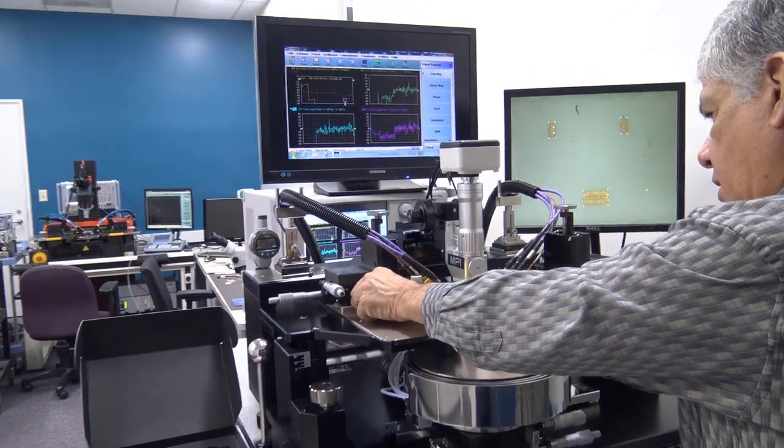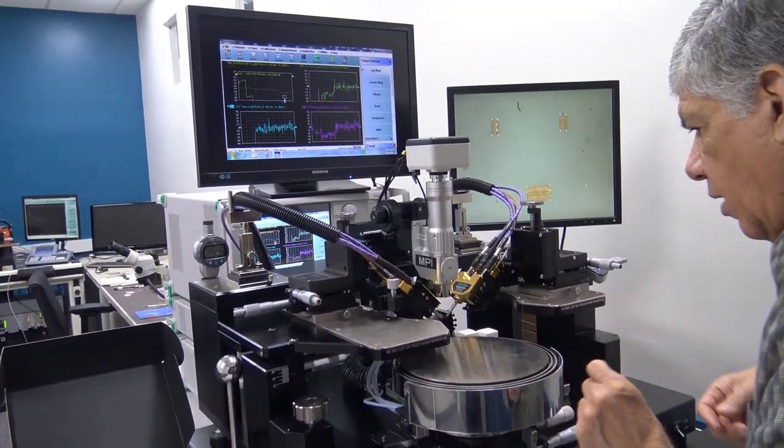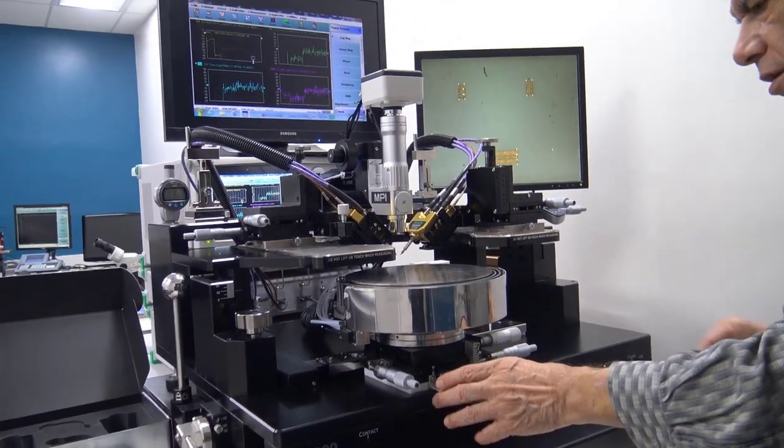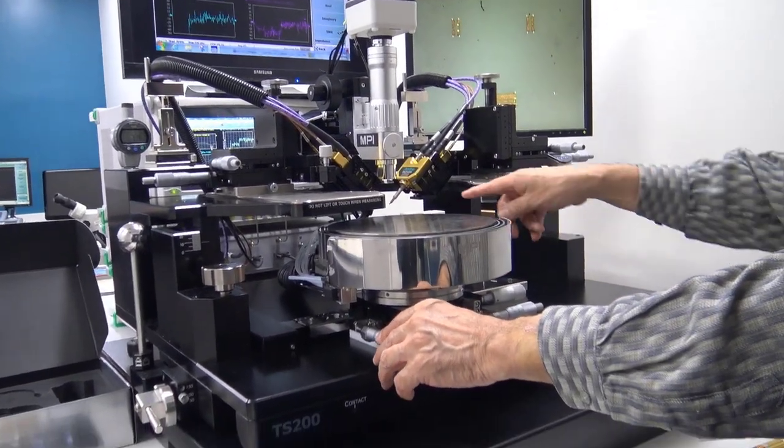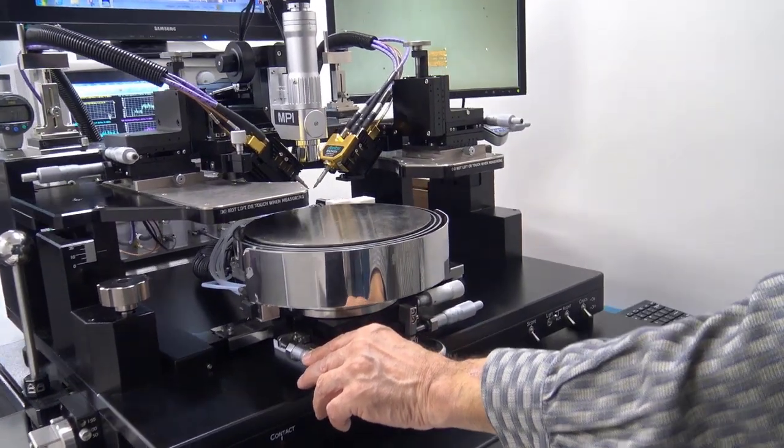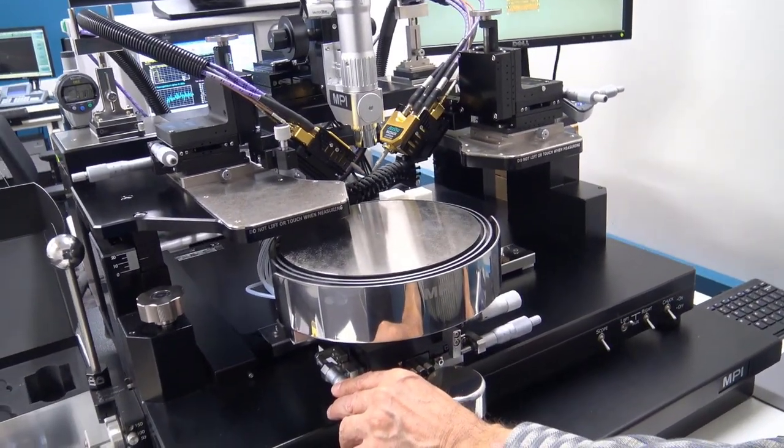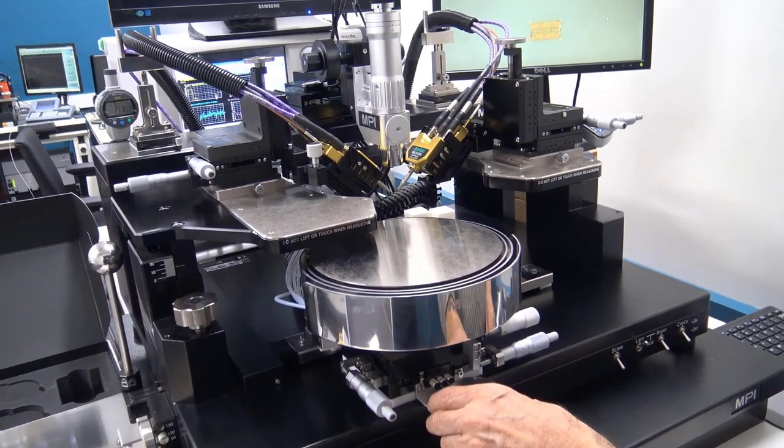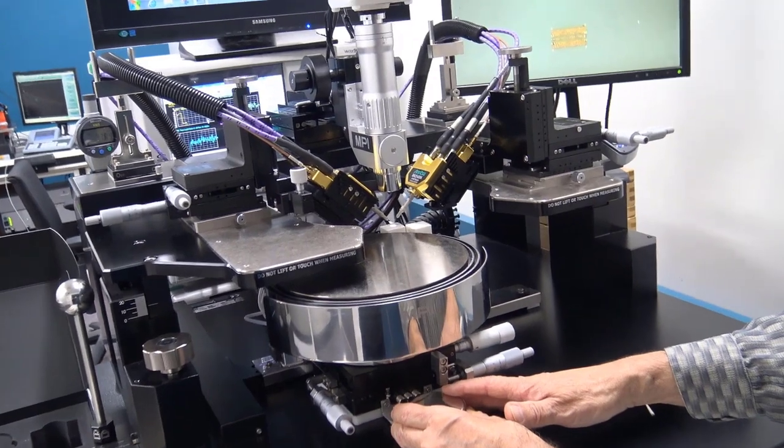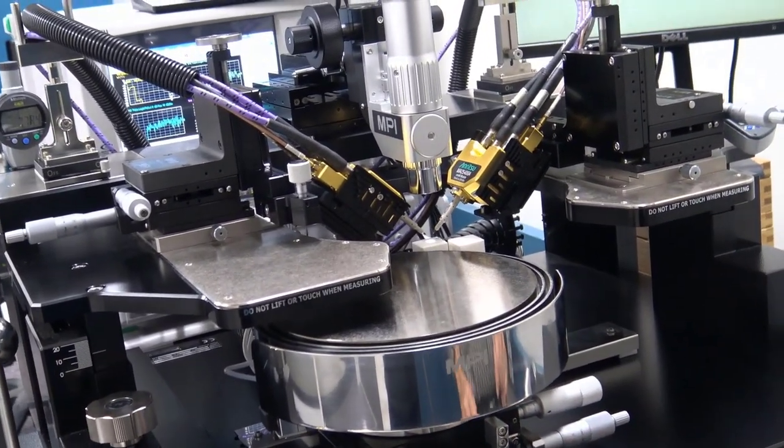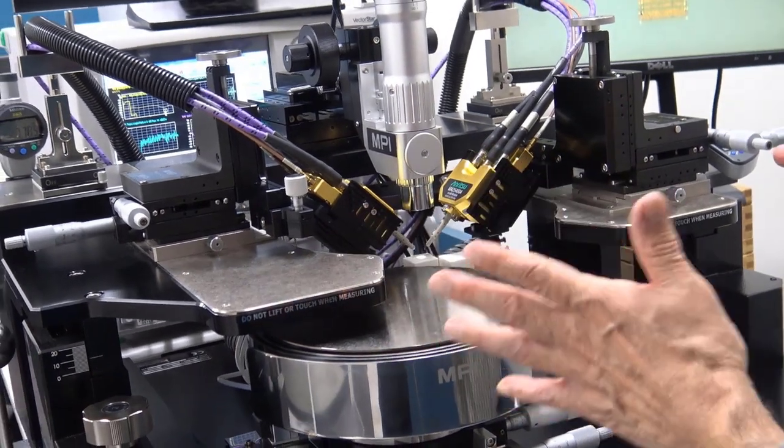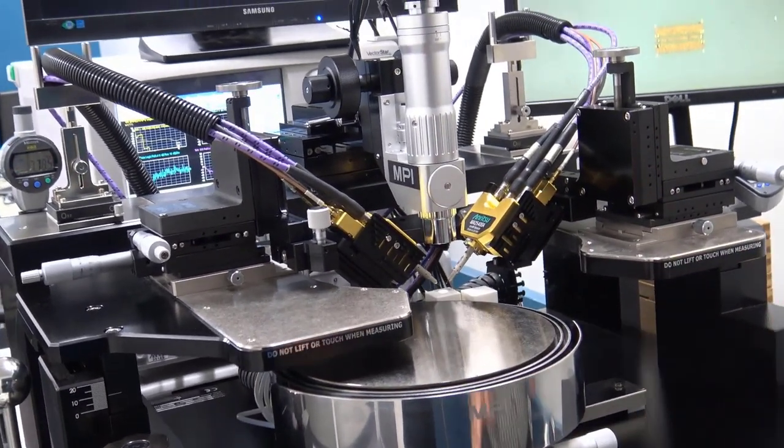And there you have it. And so the chuck has ceramic chucks for the calibration substrates, which is always a good idea to use. And so now you've got your setup ready for calibration.